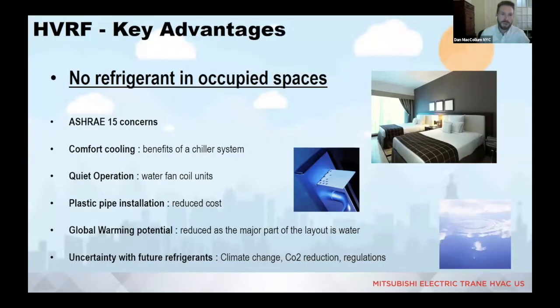So we're going to run through some of the key advantages for this hybrid VRF system. And in bold, underlined right at the top, no refrigerant in the occupied spaces. So if you've ever been involved in an ASHRAE 15, ASHRAE 34 refrigerant concentration limit calculation, as long as you can place that BC controller in an unoccupied space, you're not piping any refrigerant into the sleeping quarters or living quarters for anyone. So there no longer is an ASHRAE 15 concern for that system.